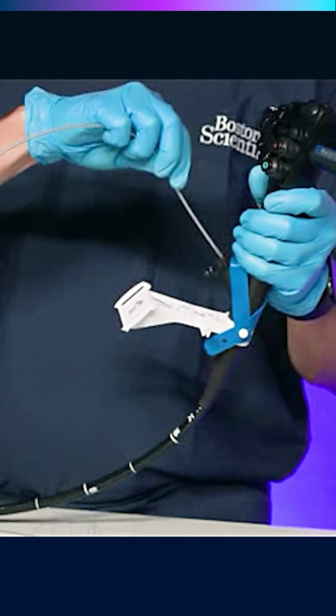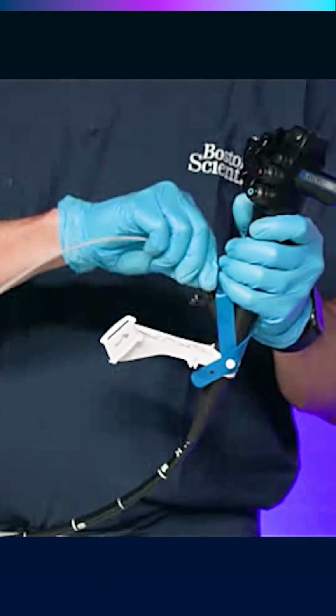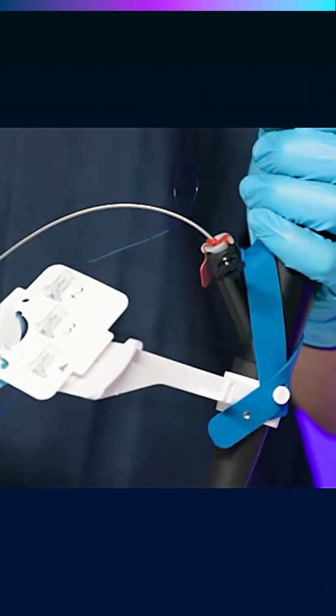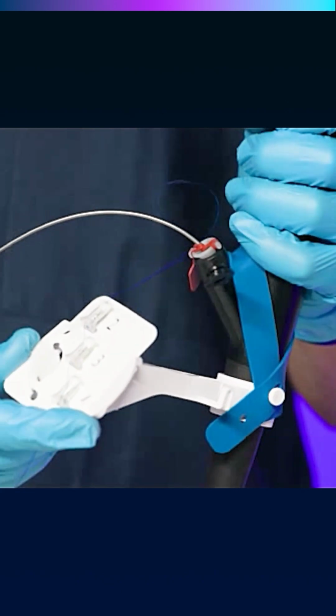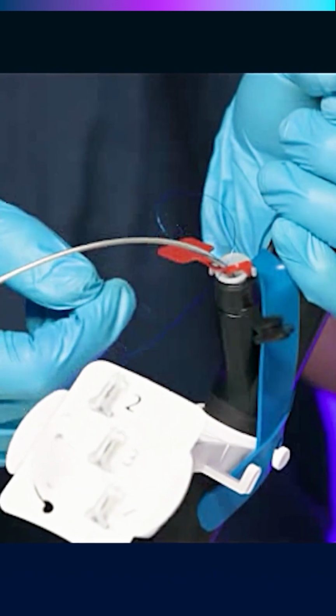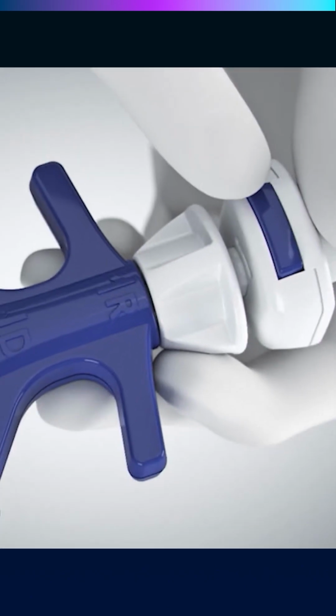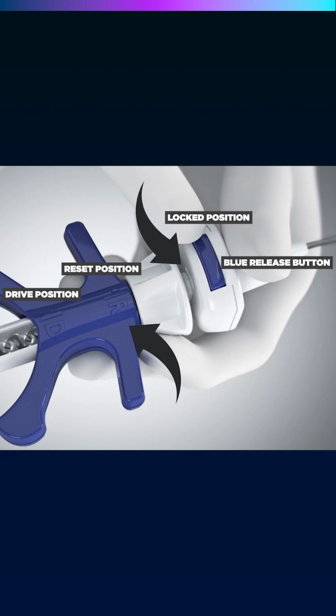Insert the X-Tack device with preloaded Helix Tack and scope liner into the scope channel. Position the backer card by inserting into both side tabs. Pull on the red scope liner clamp to release and remove. Ensure the handle slider is in the reset position and the push catheter is in the initial locked position.